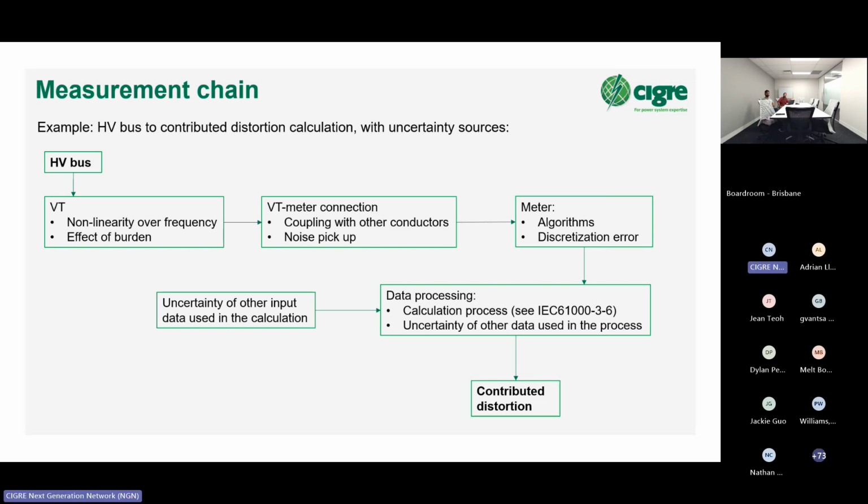But what is the uncertainty of the number that gets calculated through the measurement and our calculation process? Can we say that number is above or below the threshold? How confident are we that it is truly above or truly below? What is the probability that it is above, the probability that it is below? We need to get some statistics into this, and we need to first understand what the sources of uncertainty are, and then estimate the uncertainty. Again, it is an estimate, it's not perfect, but it's better than taking digits bluntly and comparing them and saying, no, it's above. Well, wait a second, is it always above? Is it for sure 100% that it is above?